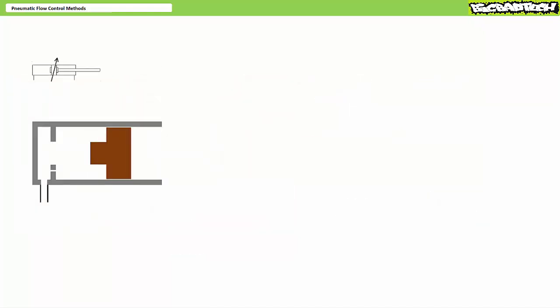Now that we've got a good appreciation for meter out flow control methods, I should mention cylinders with adjustable cushions on extension and retraction make use of this method at the very end of the cylinder stroke. Cushions allow a cylinder to move quickly through a majority of its stroke, however ease it to a nice gentle stop at the limits of extension or retraction instead of just slamming to a halt.